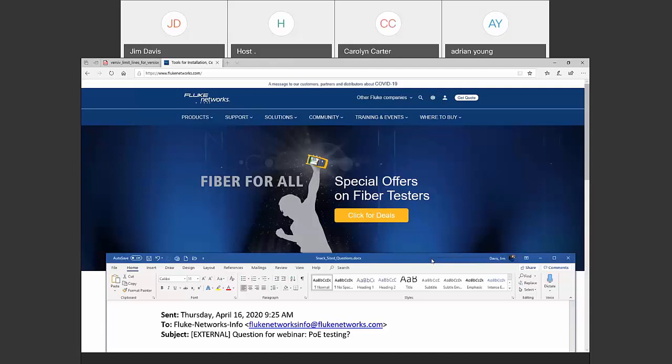And then if you push back, saying, oh mate, it's going to add so much time, that's about a second for the autotest to do that measurement. Time to consider a different installer.